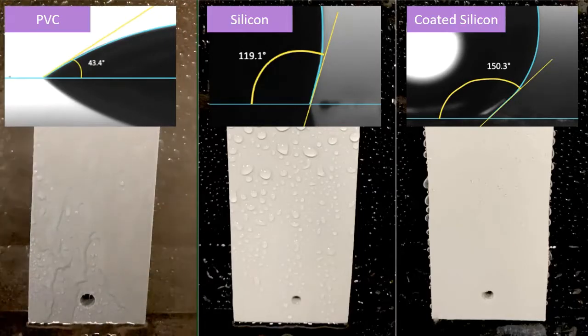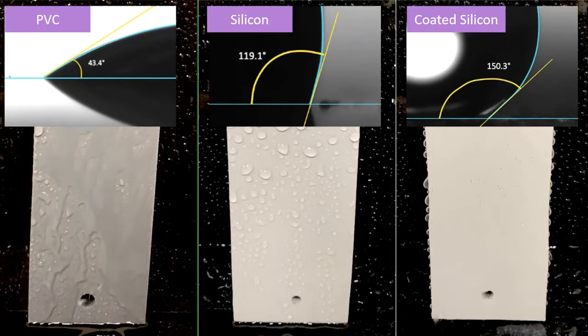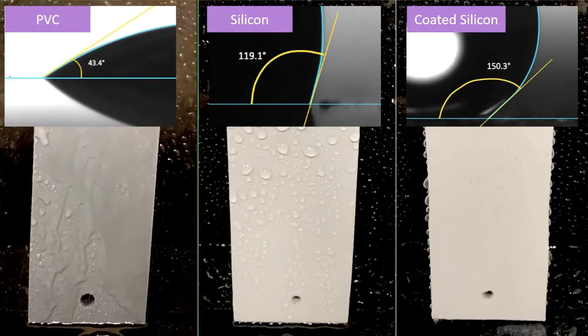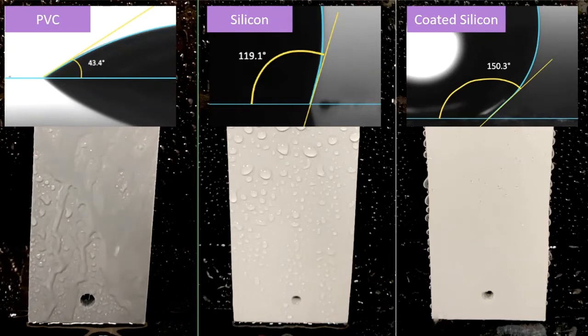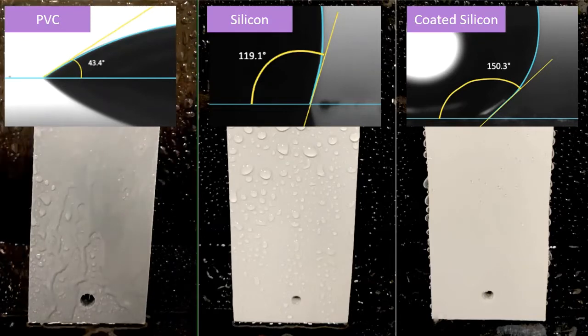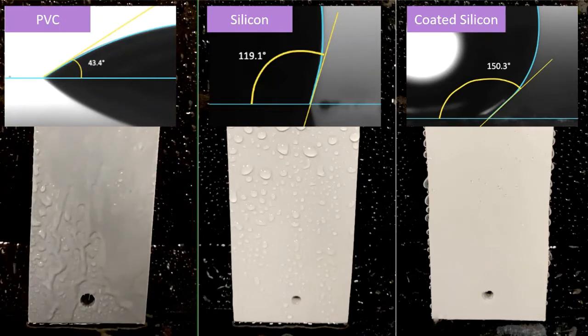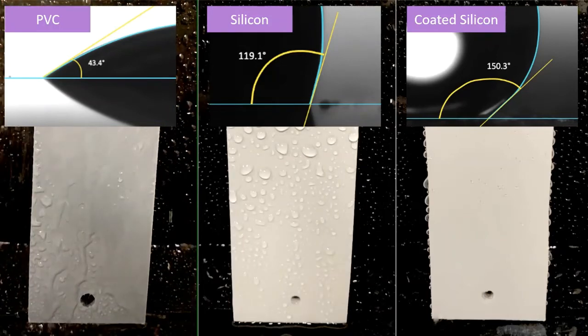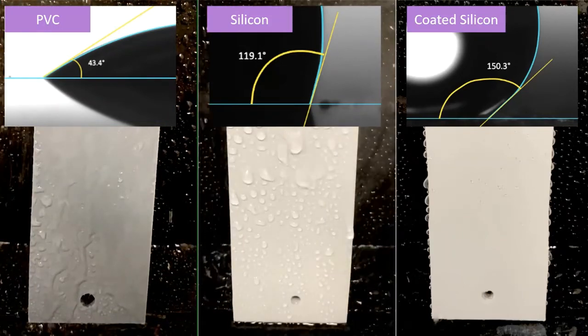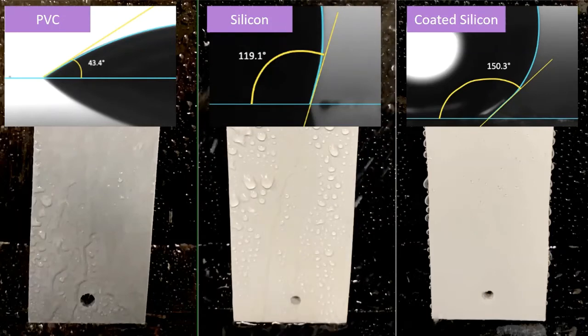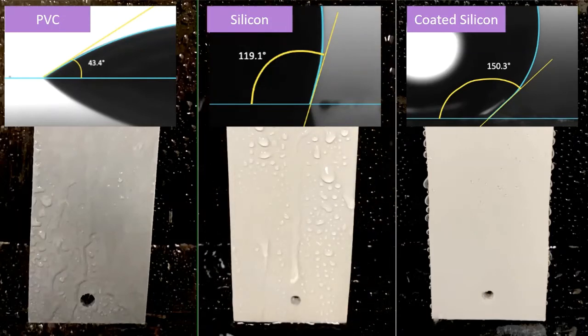Hydrophobicity is the ability of a material to repel moisture, which is measured by a contact angle. This is the angle between a droplet of liquid and the material's surface. Hydrophilic surfaces such as PVC, ceramic, and glass are defined by a contact angle smaller than 90 degrees. Hydrophobic surfaces such as silicon rubber have a contact angle greater than 90 degrees.